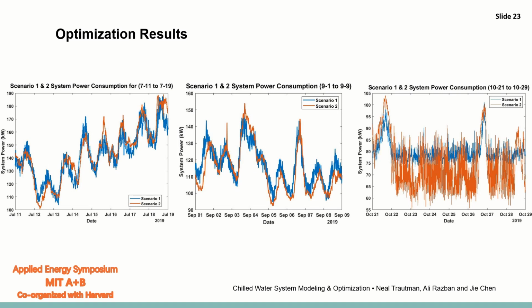Here are the results. So for the first 2 weeks, scenario 1 and 2 should actually be equal, since in the baseline, both the condenser water pump and the cooling tower fan ran at 100% until we reached October, at which point in scenario 2, the cooling tower fan began to cycle. As you can see, scenario 2 is actually lower than scenario 1, which means that cycling the cooling tower fan increased the efficiency of the system and actually saved them money, as opposed to running the cooling tower fan at 100% year-round.